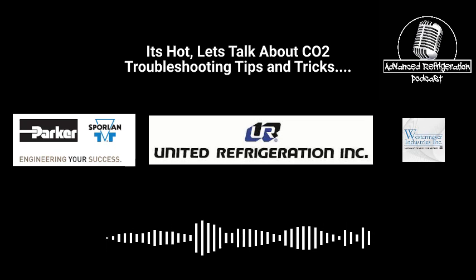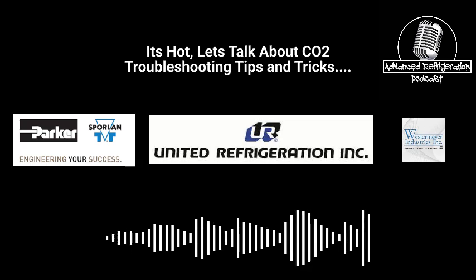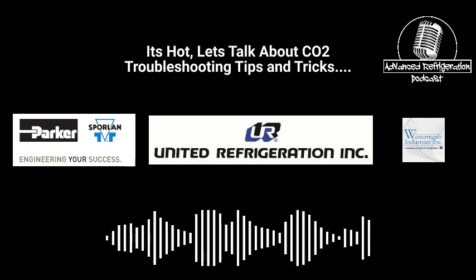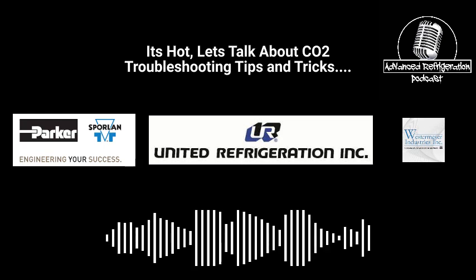Don't plug your laptop in, especially if you're at a customer where they have all the controllers going to a router and then one comm line. Unplug the store comm line and then do all that. But no, that's how we've been doing these, and it's a pain in the ass. It sounds like it. And then some things don't transfer over. So like EPRs, separates don't transfer over. Oh, that sucks. So you got to go through every single one and then make sure everything's good.